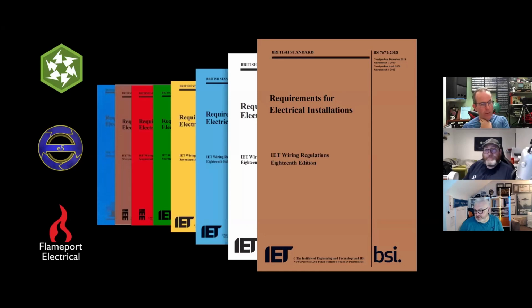Sean says, surely if we use the data tables for appliance leakage, then all offices would require high integrity socket outlet circuits. If we added them all up, yes - I guess the issue is you may have to apply diversity to that. Either way, the subdivision in the installation is just going to keep going on. It's something we're going to end up RCBOing.